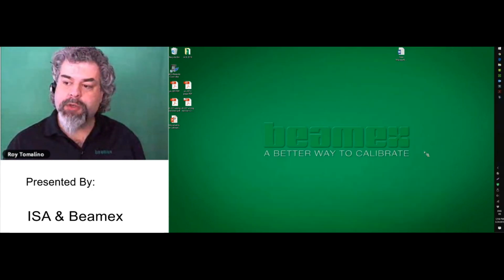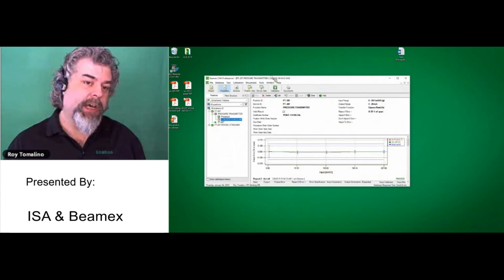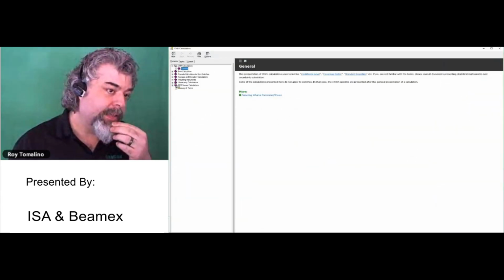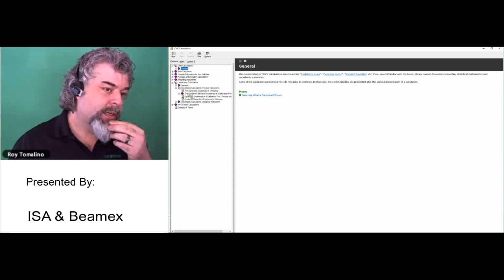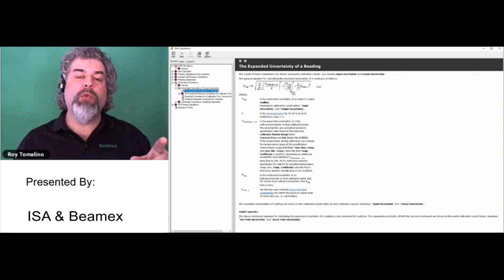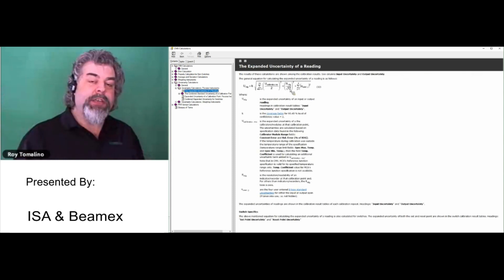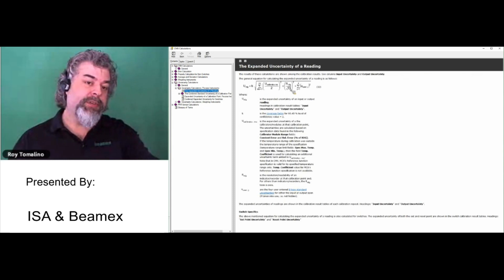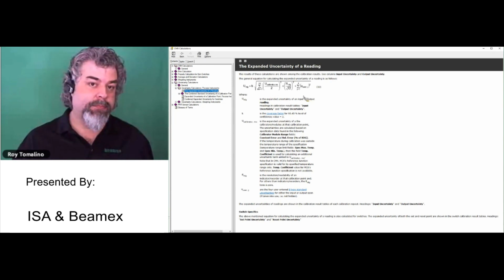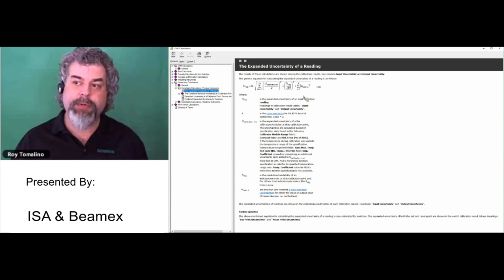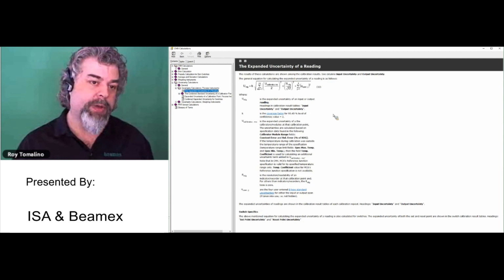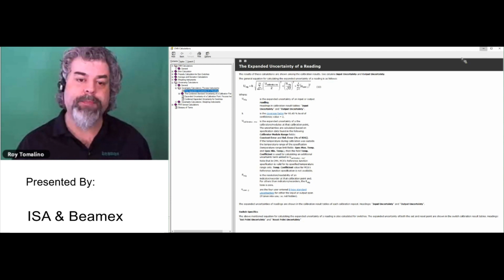One other thing let me show you is inside the software. Your software should be able to calculate uncertainty. If you want to, you can not use software that does this, and you can grab this formula and add it all up, do the math. But for me, I'd rather have the software do it for me. So this is the expanded uncertainty of a reading.